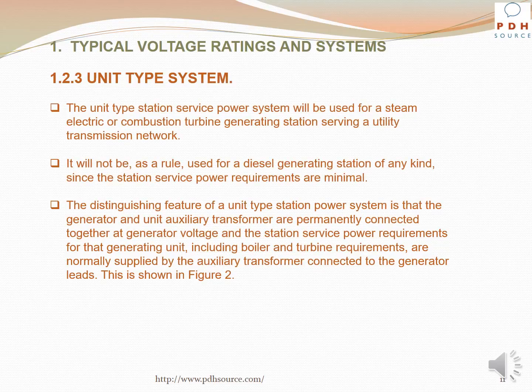The unit type station service power system will be used for a steam electric or combustion turbine generating station serving a utility transmission network. It will not be, as a rule, used for a diesel generating station of any kind, since the station service power requirements are minimal.